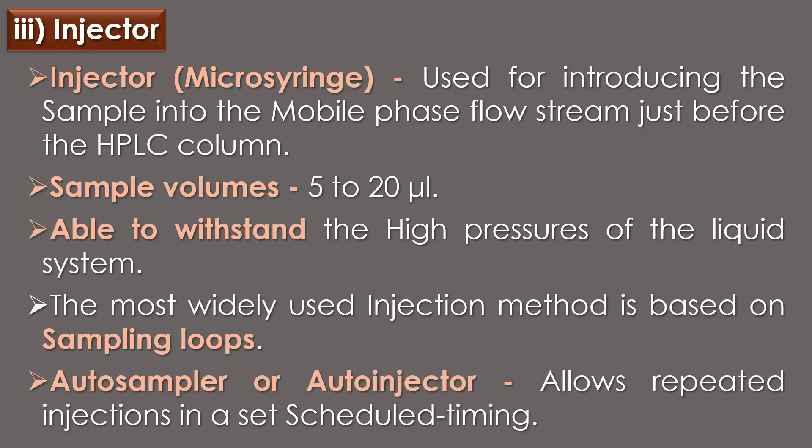An injector is placed next to the pump. Usually a micro syringe is used for introducing the sample into the mobile phase flow stream just before the HPLC column. Typical sample volumes are 5 to 20 microliters. The injector must also be able to withstand the high pressure of the liquid system. The most widely used injection method is based on sampling loops, and the use of an auto sampler or auto injector is also widely used, allowing repeated injections at scheduled times.